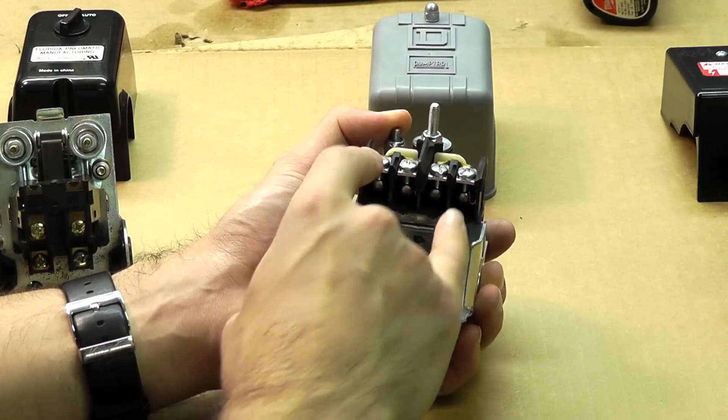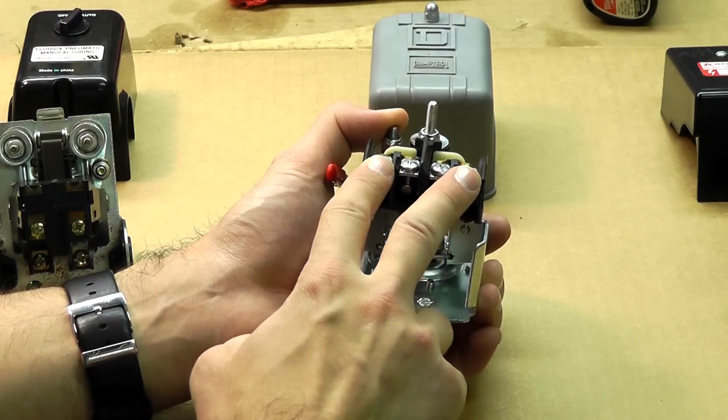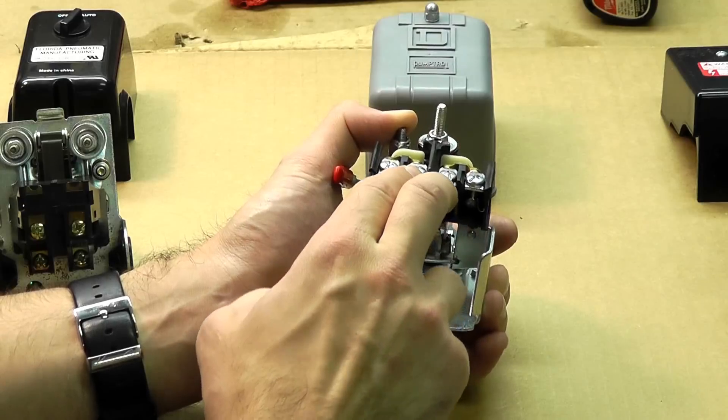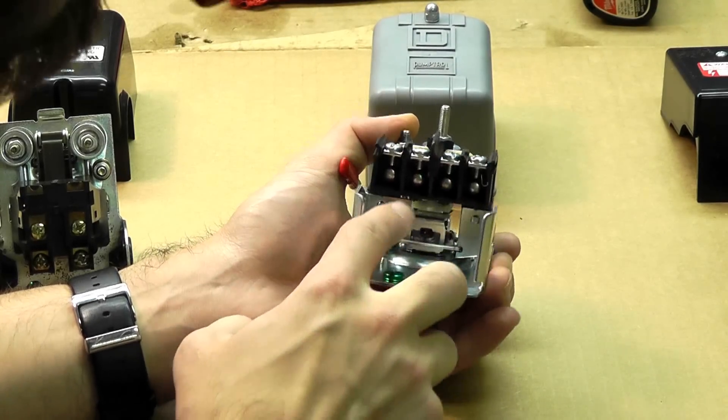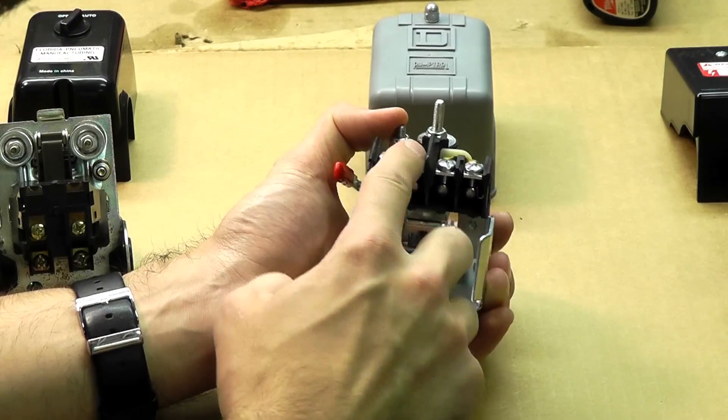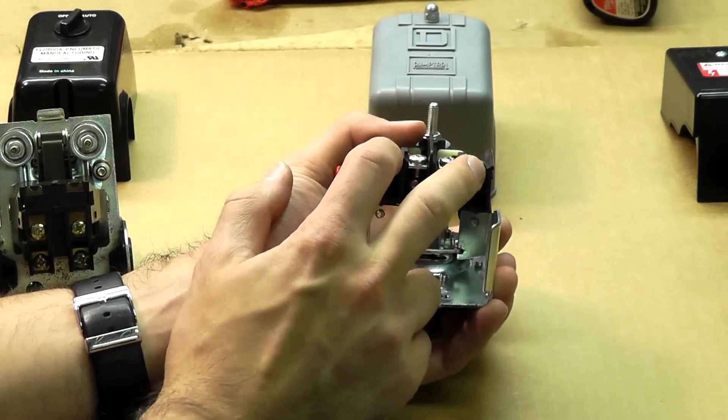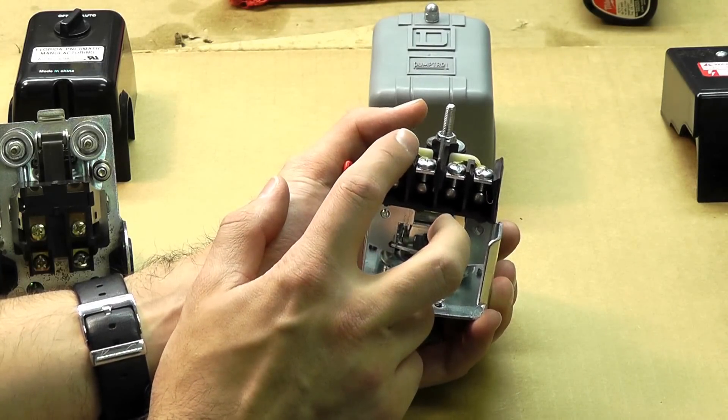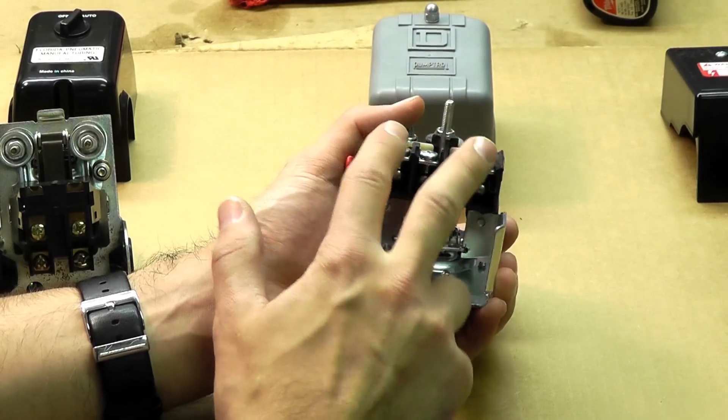So what you'll do is, if it's not labeled line or motor, you want to install your line or power cord wires on the outer contacts, on the outer terminals. Keep them on separate contacts and of course your motor wires on the inner terminals. So then you have power cord on one and three, and your motor on two and four.